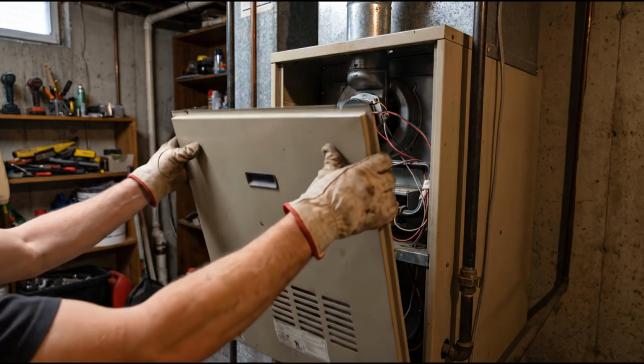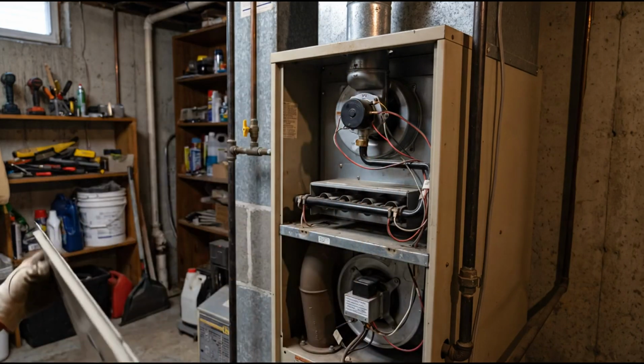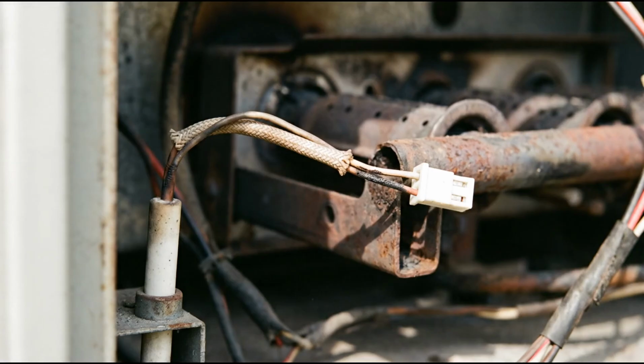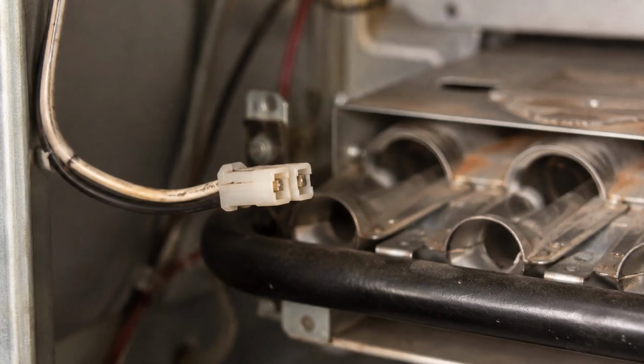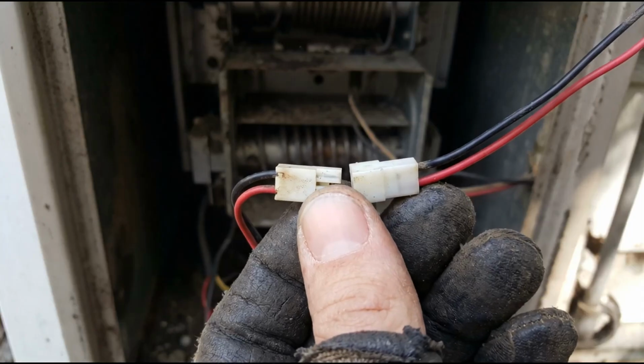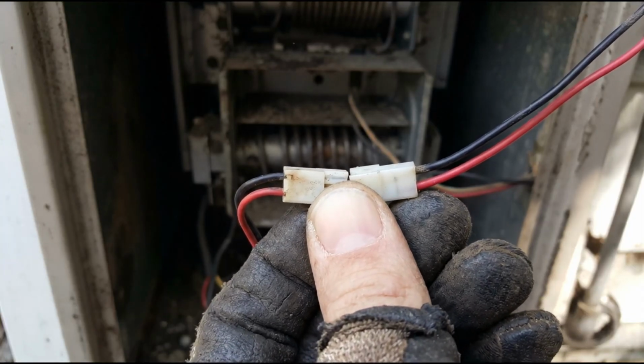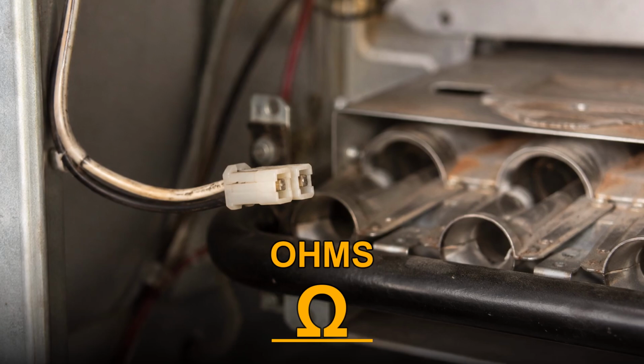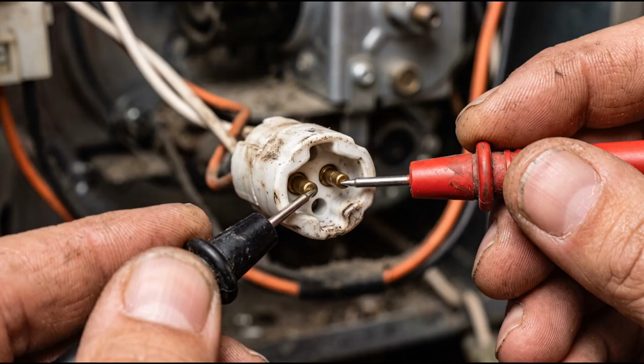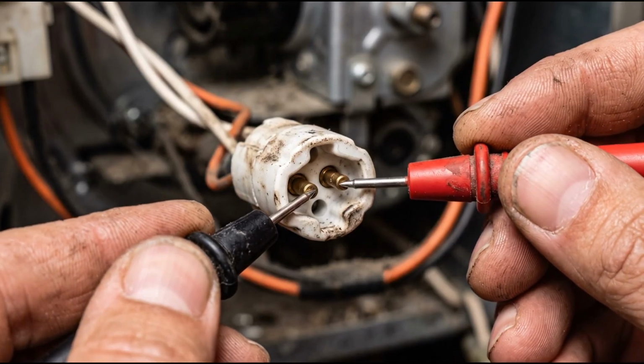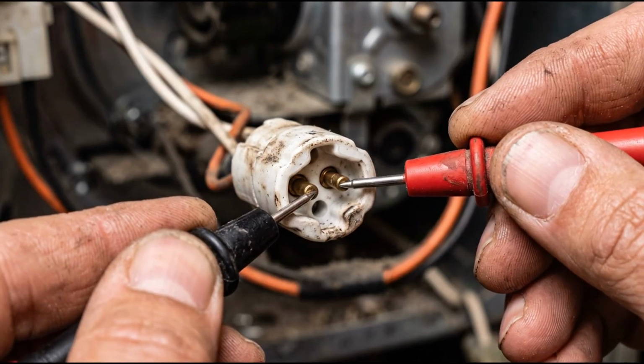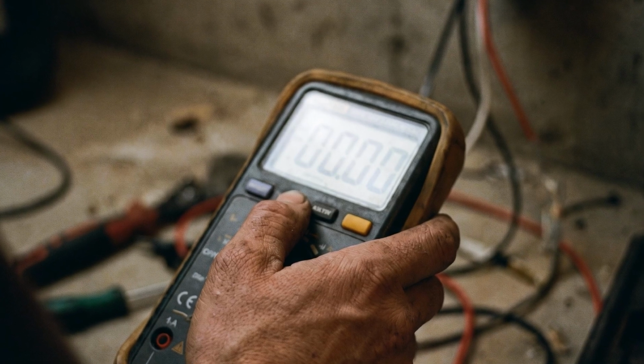Take the door off the cabinet. The igniter sits right at the burners, at the end of a short 2-wire lead with a small plug. Unplug that connector. It pulls apart. No tools. Set your meter to ohms, that is the horseshoe symbol, and touch one probe to each pin on the igniter side of the plug. Here is what the numbers mean.